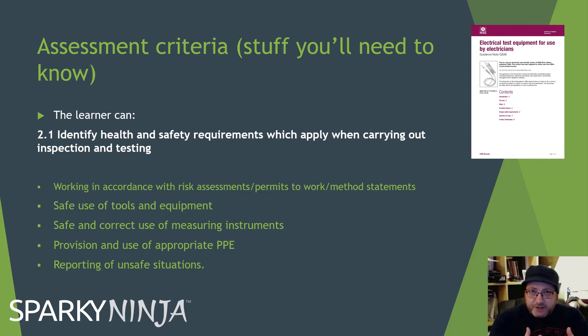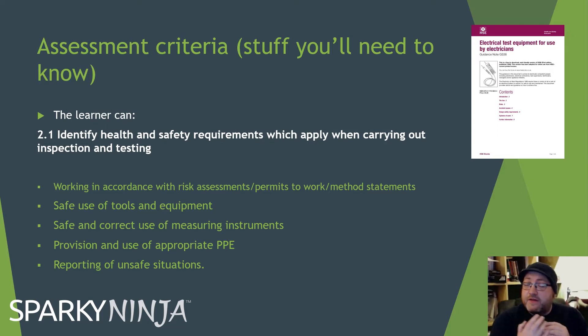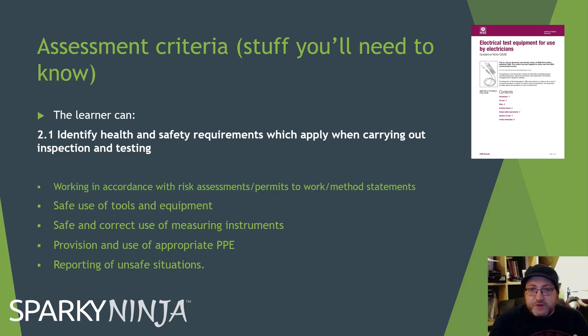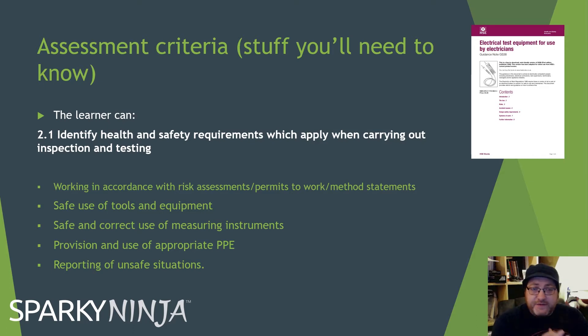You carry out a risk assessment, develop a system of work, then look at the site — whether it's domestic, industrial, or agricultural. Make sure they all work together. This should all be done at the pre-survey point. You'll determine what tools and equipment you're going to use. Standard multi-function testers (MFTs) should be in good condition, good repair, with charged batteries, calibrated, and sensible — with insulated tools.